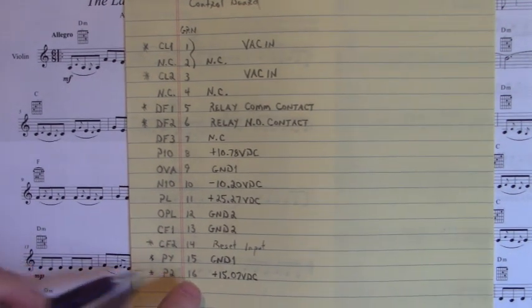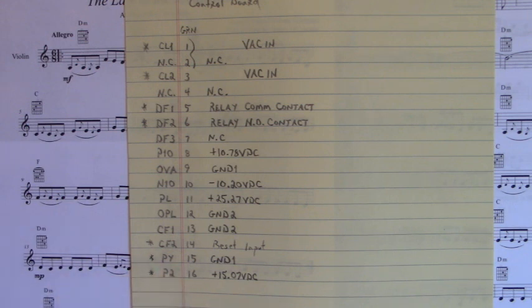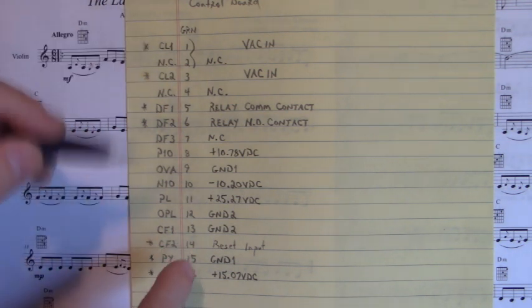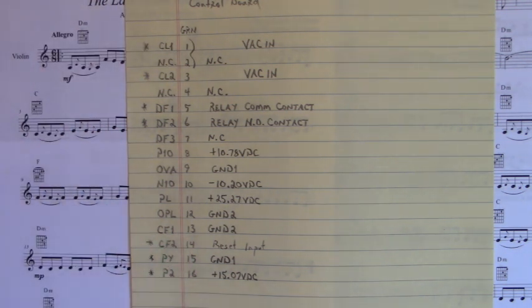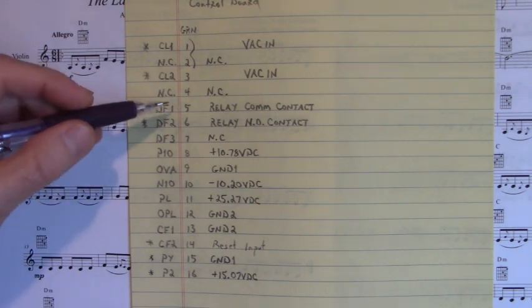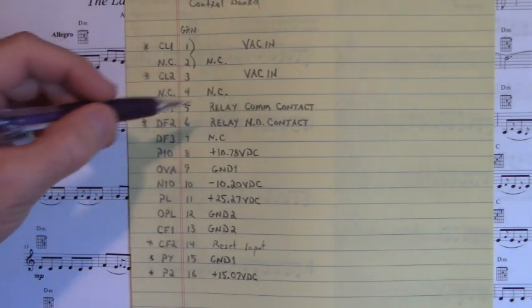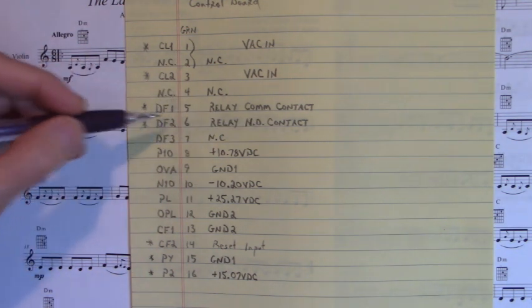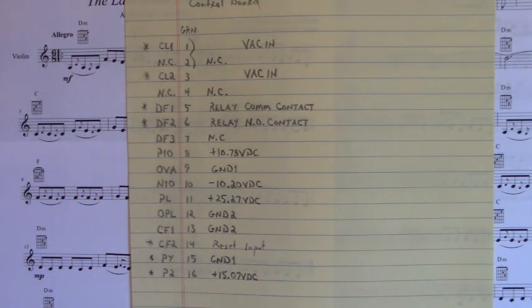Now this is an output. I'm not sure where it goes to. If I had the whole machine here, I could tell you where that goes to. But it's probably seriesed with another thermal in the machine. And if that thermal switch in the machine, wherever that's at, opens up, or the heat sink inside the power supply opens up, we get a thermal alarm. And up here on the relay common contact and relay normally open contact, they would probably close because of the alarm.